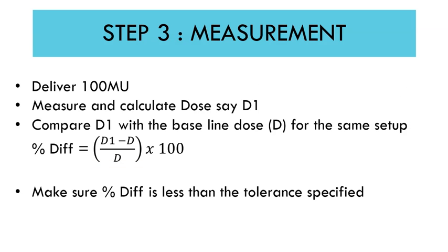Then do the measurement. Let's say you deliver 100 MU, measure the ionization or the dose, and calculate the dose value, let's say it's D1. Then compare that D1 with a baseline value, let's say that's D.